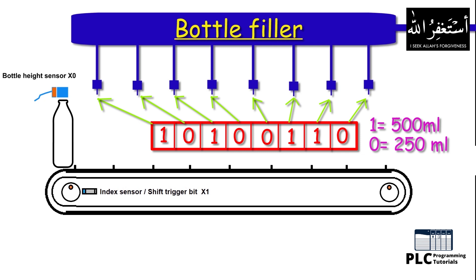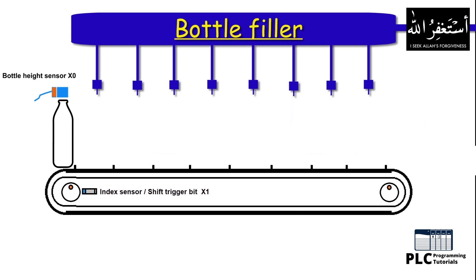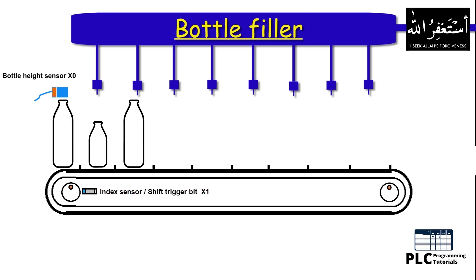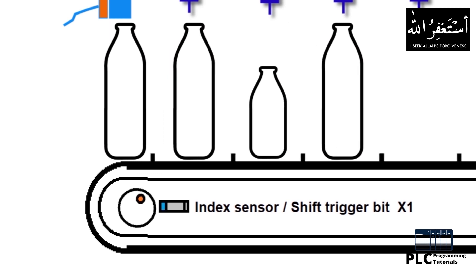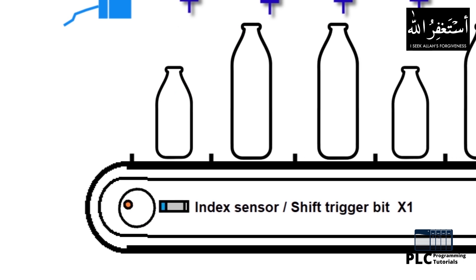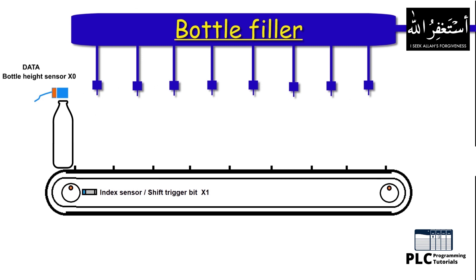Data bit one indicates a 500 ml bottle, and data bit zero indicates a 250 ml bottle under the filling nozzle. Next, we have a bottle height sensor which is either on or off — it turns on and gives a one for a 500 ml bottle, and remains off giving a zero for a 250 ml bottle. We also have an index sensor on the conveyor which is activated once for every rotation of the gear, indicating the conveyor belt has moved one step forward. We can use this sensor signal as a trigger to shift the data bits across the shift register. Let's see the complete animation and understand how the whole concept works.